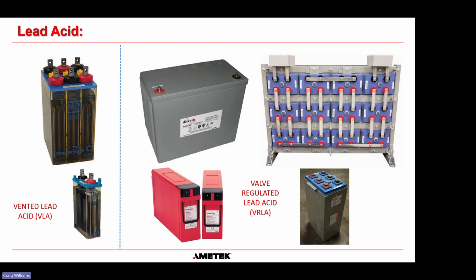And for lead acids, there are many different variations. On the left-hand side, what we call our vented lead acids, and that is when you can see inside the cell. Some other people call them wet cells. It's when you can see the electrolyte inside, and there are usually flame arresters here. We've got vent caps here for shipping, but if they have flame arresters here, they actually do vent hydrogen into the atmosphere when they're being charged.